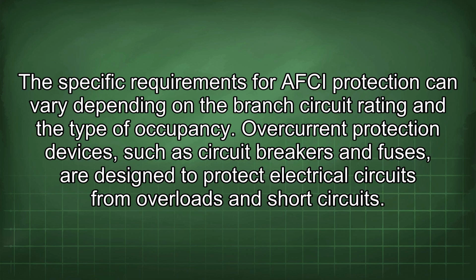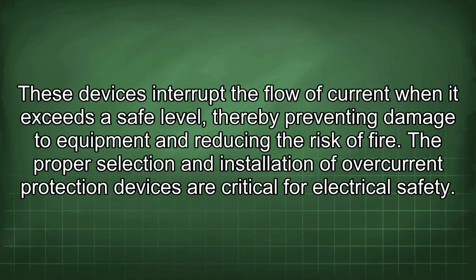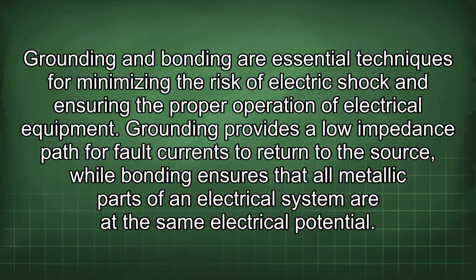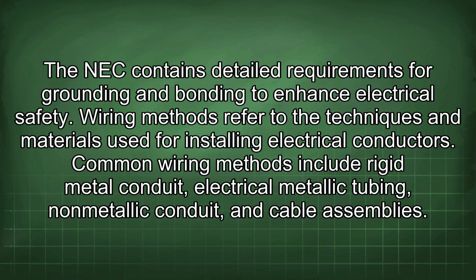Overcurrent protection devices, such as circuit breakers and fuses, are designed to protect electrical circuits from overloads and short circuits. These devices interrupt the flow of current when it exceeds a safe level, thereby preventing damage to equipment and reducing the risk of fire. The proper selection and installation of overcurrent protection devices are critical for electrical safety. Grounding and bonding are essential techniques for minimizing the risk of electric shock and ensuring the proper operation of electrical equipment. Grounding provides a low impedance path for fault currents to return to the source, while bonding ensures that all metallic parts of an electrical system are at the same electrical potential. The NEC contains detailed requirements for grounding and bonding to enhance electrical safety.